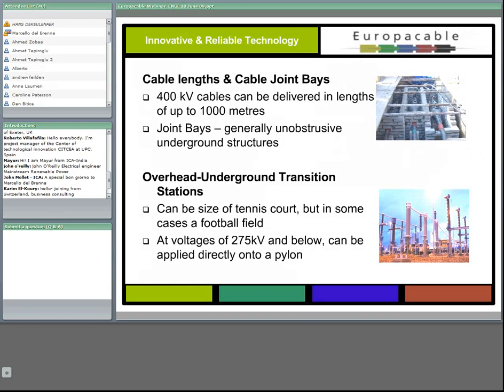Another myth often considered a technical block is the overhead-underground transition station, which can be the size of a tennis court, maybe a little bigger, depending on the philosophy of the utility and the equipment used. But at 275 kV and below, transitions can be applied directly on pylons, as we've seen in France and other countries, where the transition takes very limited space.